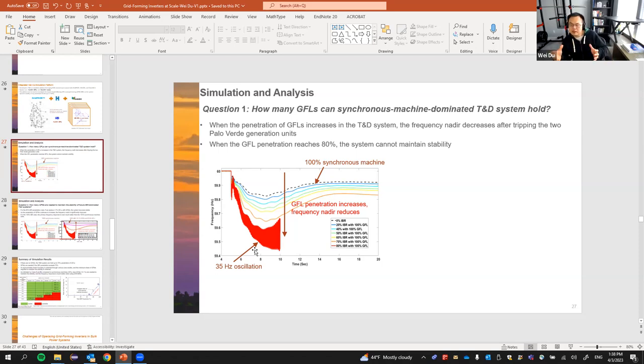After further investigation, I think that is because of your inverter control at the transmission level. When the system becomes very weak, it caused some 35 hertz oscillation caused by the grid following inverters. That voltage control loop cannot maintain the stability when the synchronous machines become less and less. So, I think that's one thing.